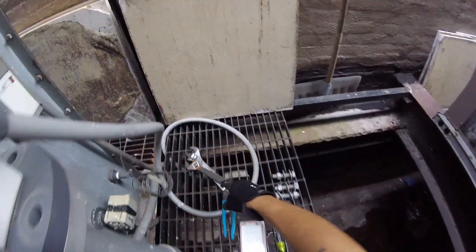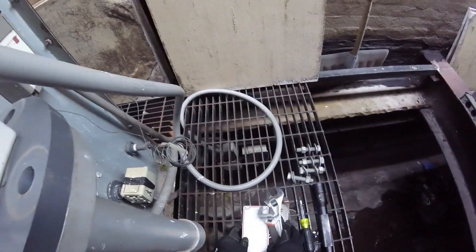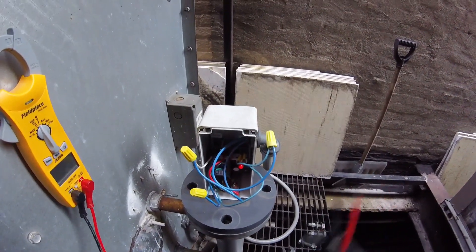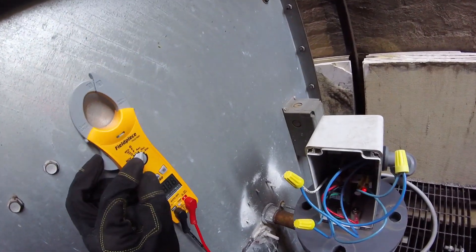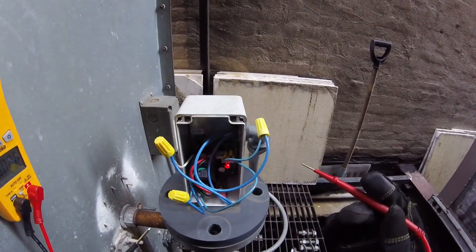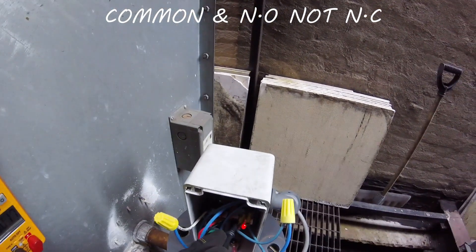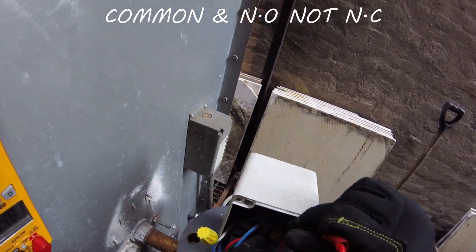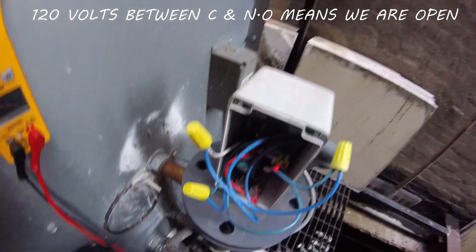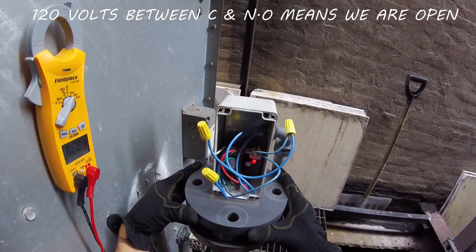Everything's taken apart. We do have an electrical whip here so we can lift this with everything connected. We're connected to a common and a normally open. Let's check between those two and see what we have — we have 120 volts. We are open.